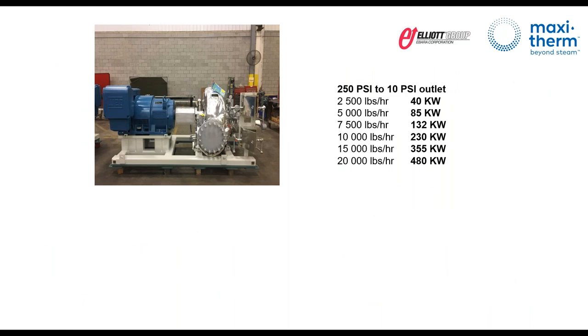Related to the flooded heat exchanger design, if we're talking about a typical pressure reducing valve, or PRV, replacement application, Patrick and I talked about looking at just average loads. So for these average loads that you see here at various increments, we took 250 PSI saturated steam and dropped it through a valve down to 10, whether for heating needs or deaerator purposes. We looked at what the actual performance would be of a turbine generator at these various average loads. The numbers you see here are accurate numbers that we took out of our performance program, just to give you some real data.